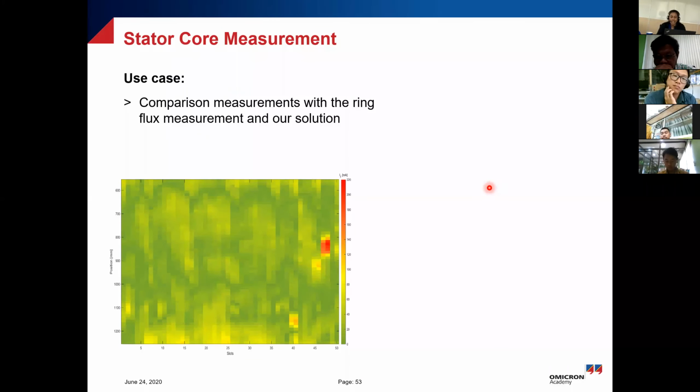And the other thing is the expected lifetime for the generator. In your experience, how many years has a generator in a power plant been used, more than 40 years, or less than that? I have seen up to 40 years. After 40 years, I had a case where one portion of the core basically melted completely. And there is a lack of information as well.